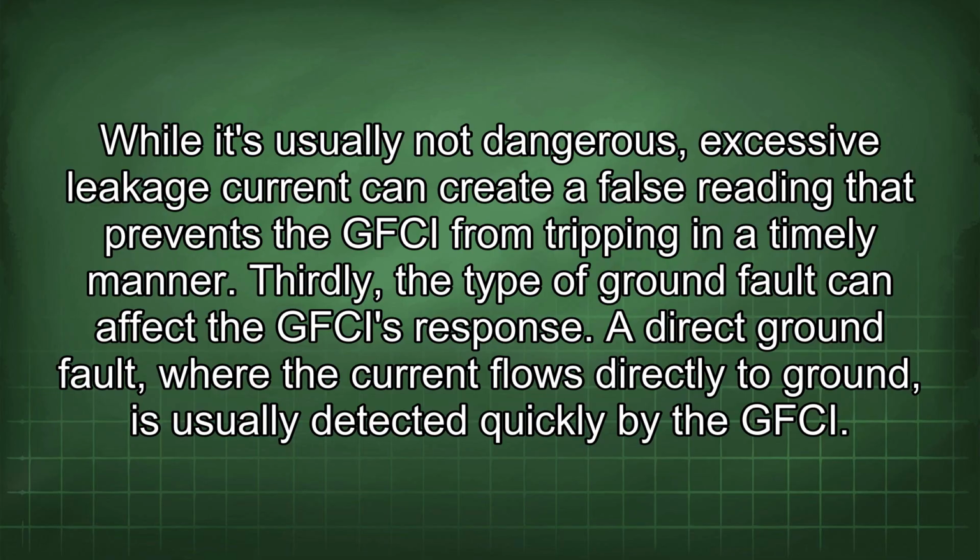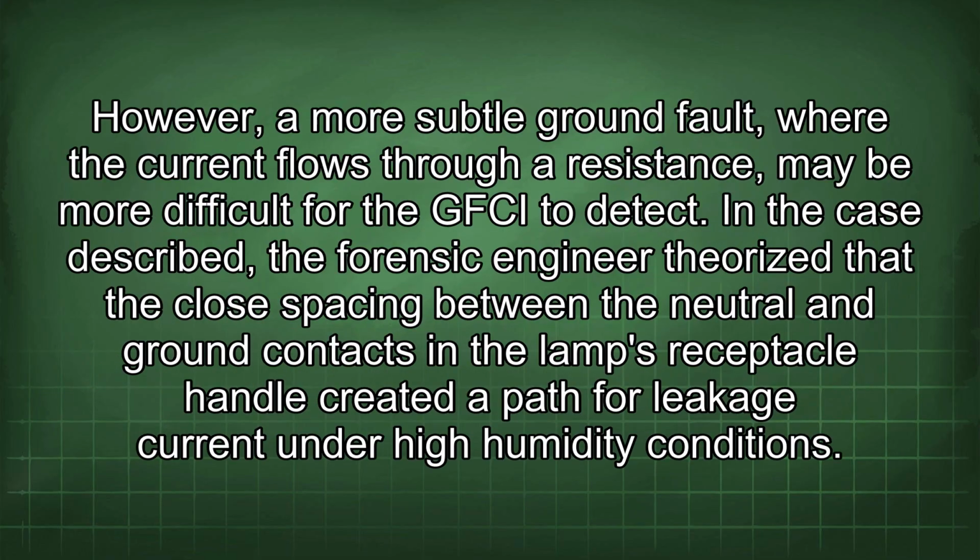A direct ground fault, where the current flows directly to ground, is usually detected quickly by the GFCI. However, a more subtle ground fault, where the current flows through a resistance, may be more difficult for the GFCI to detect.